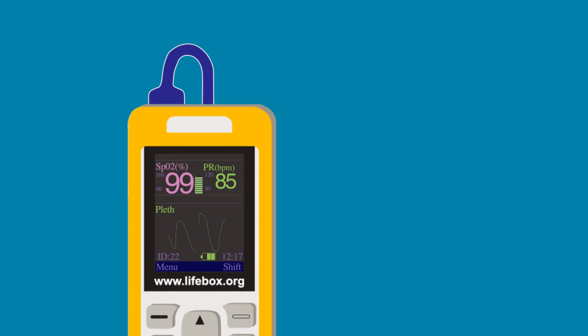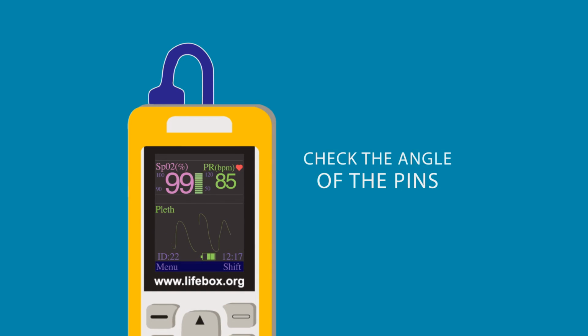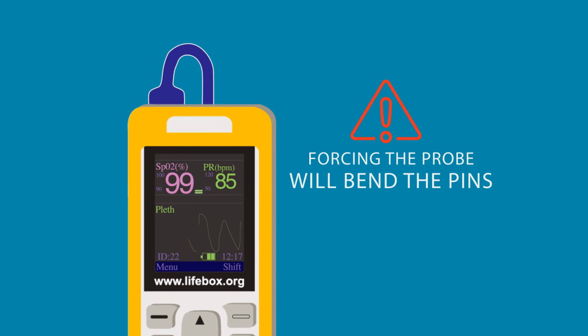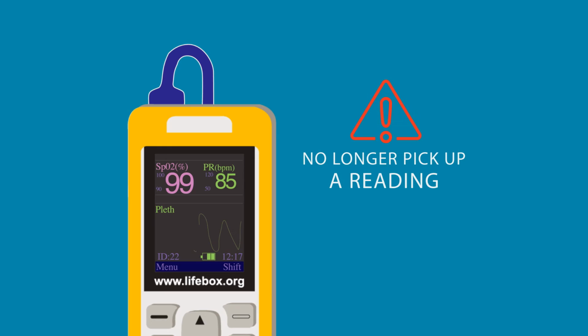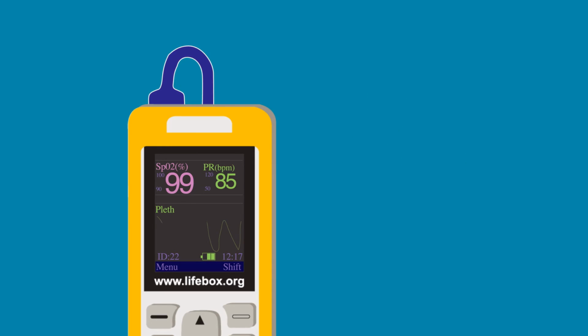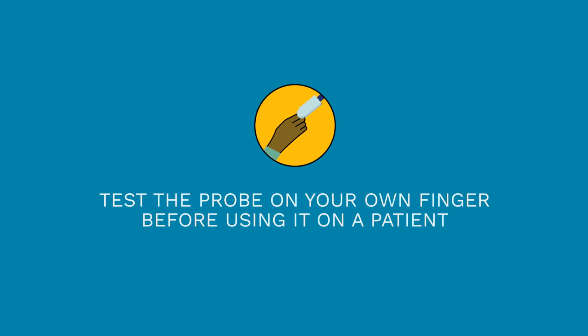It is very important that you check the angle of the pins and the angle of the receiving end of the oximeter before trying to connect the two. If you force the probe in upside down, you will bend the pins and the probe will no longer pick up a reading. When disconnecting and connecting the probe, grip the end firmly. Do not pull the cable to prevent the small wires inside from tearing. Test the probe on your own finger before using it on a patient. Assuming you are healthy, you should get normal readings for your oxygen saturation and heart rate.